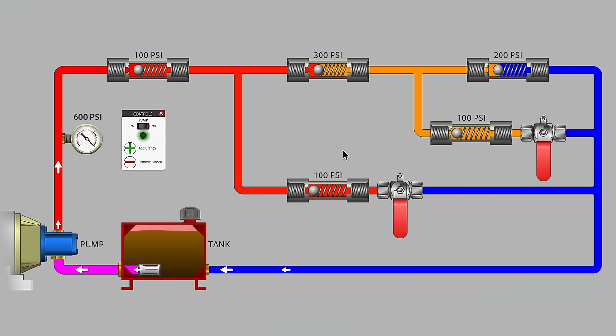And if you knew what all of the rest of your expected pressure drops add up to, you would know that since you're receiving a 600 PSI system pressure value on the system gauge, that the only branch where flow is occurring at this moment must be along this top branch here. Of course, you can't see inside hydraulic systems as you can on these animated models. So, gathering up information about normal expected pressures for your hydraulic system really helps you when it comes time to troubleshoot.